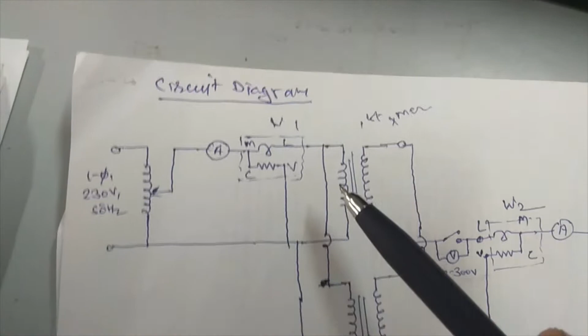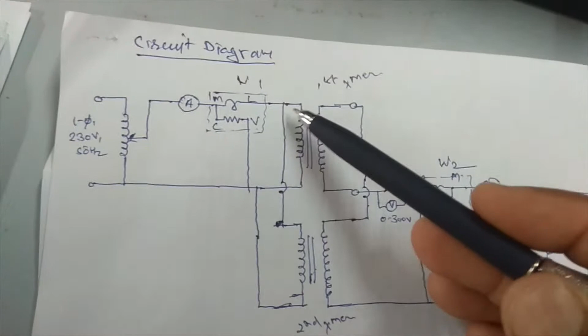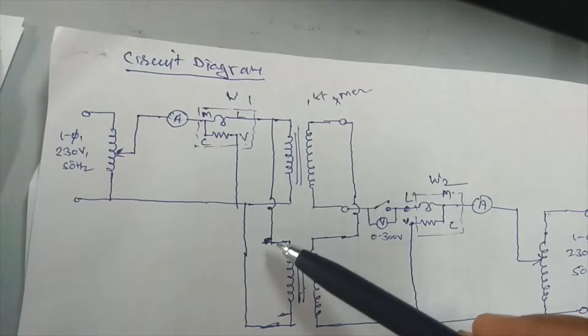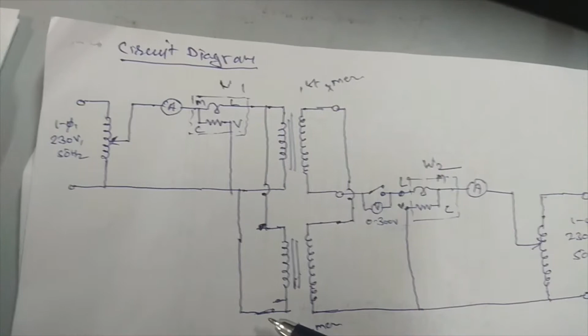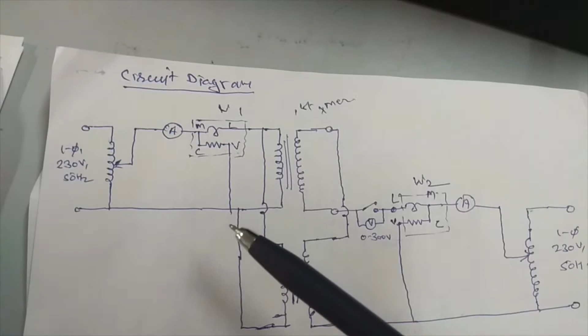Next we connect this in parallel to the second transformer's primary. The two wires from the first terminal of the primary of the first transformer are connected to the first terminal of the primary of the second transformer, and the other terminal is connected to the other terminal of the second transformer. This is the connection on the LV primary side.